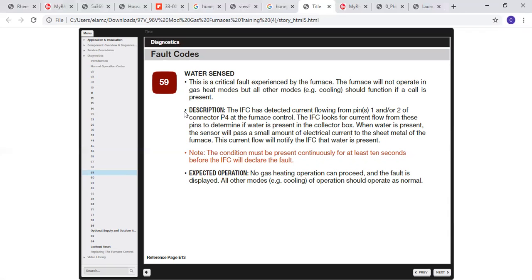Also, if you have PVC shavings, I've seen that before, get back in the secondary collector box. If there's such a buildup in there, it can actually create the short or create the ground from the water sensor to the secondary exchanger. So sometimes pull those out, look in there, and take a piece of thermostat wire and make sure there's nothing behind there.